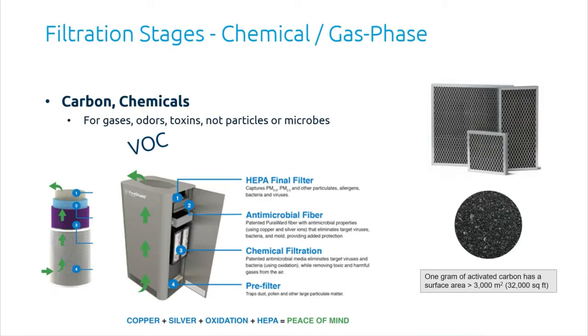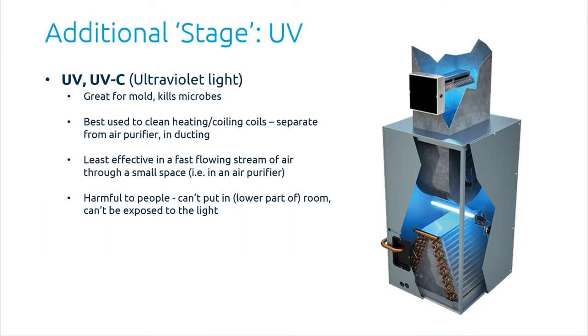As a second stage, you may have chemical or gas phase filtration, as I mentioned. The difference between carbon and chemical: carbon captures odors, no problem. Chemical can capture odors the same way, but also kill viruses and microbes. So oftentimes you might want a chemical media ahead of your HEPA filter, so you're killing viruses before they even reach the HEPA. It's just an auxiliary system you can have in your air purifier.